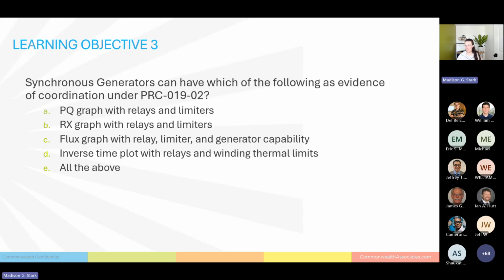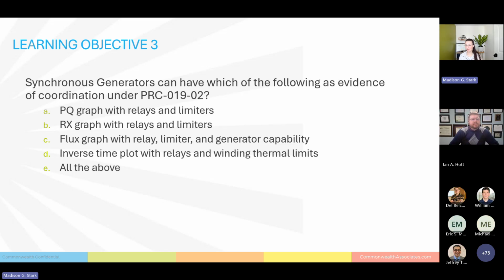All right, so that kind of wraps up what we cover for synchronous generators. Dell, if you want to roll poll 3. I know there was a lot of information. Yep. Question 3. Synchronous generators can have which of the following as evidence of coordination under PRC 19-02? A PQ graph with relays and limiters, an RX graph with relays and limiters, a flux graph with relay, limiter, and generator capability, an inverse time plot with relays and winding thermal limits. Vote now. All of the above is also an option.